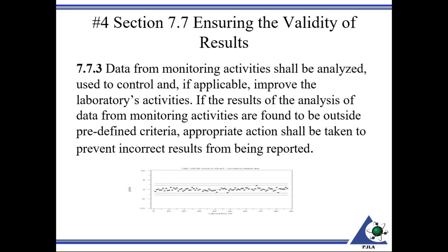And also your data. I've seen proficiency testing where it was even just, here's our data and here's their data. Bang, we're done with our proficiency testing. No. You have to analyze the data. So in other words, what's that data showing? Were you in agreement? Were you not in agreement? So it shall be analyzed, used to control and, if applicable, improve the laboratory activities. If the results of analysis of data from monitoring activities are found outside of predefined criteria, appropriate action shall be taken to prevent incorrect results from being reported. So you're required to perform these requirements specified in 7.7. If you're comparing your results to another organization and they don't agree with each other, the buck doesn't stop there. An investigation has to be performed, and if needed, corrective action may need to be taken.